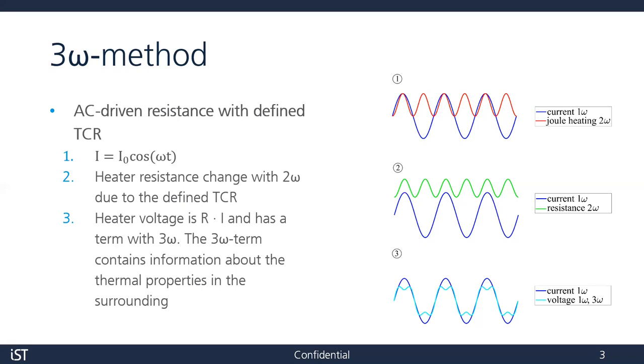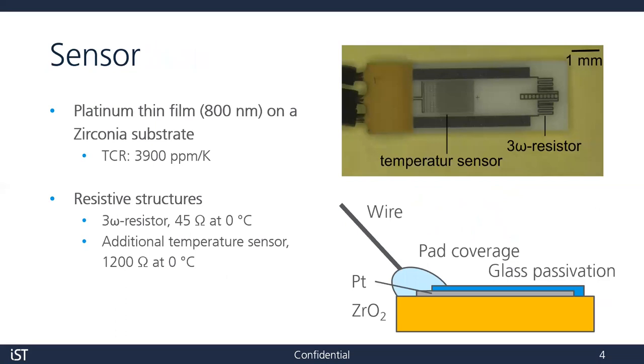It has to be noted that the resistor is both the heater and the sensor. We used a platinum thin film element applied on a zirconia substrate, structured by standard thin film lithography. Afterwards, the sensitive thin film is covered by a protective glass layer. Platinum is chosen because it has a relatively high temperature coefficient of resistance — in this case around 3900 parts per million per kelvin — and it shows superb long-term stability.